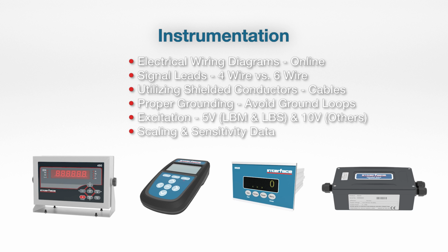Excitation voltage, as Brian discussed earlier, on the calibration certificate, in the test conditions portion, will reference the voltage of excitation that the load cell was calibrated at, and typically that would be a recommendation for usage. So if a load cell was calibrated at 10 volts, we would recommend operating it at 10 volts. Some of our smaller load cells, such as an LBM or an LBS load cell, due to the small size, may require a little bit less excitation. They may have a nominal excitation of 5 volts instead of 10. This would be to eliminate any potential for heating in the gauges.